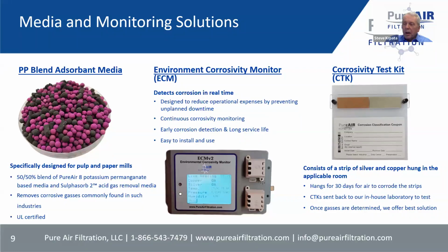It also will report on temperature and humidity. If you'll recall, those are two of the four legs of the corrosion stool, if you will. So we want to try and keep the temperature around 72 degrees Fahrenheit and the relative humidity around 45%. Then the fifth element that this device reports on is room pressure. So that would be the only thing you'd have to do when this is installed: you'd have to run a reference tube outside the space to give you a differential pressure reading. And people have different target pressures that they're trying to get.